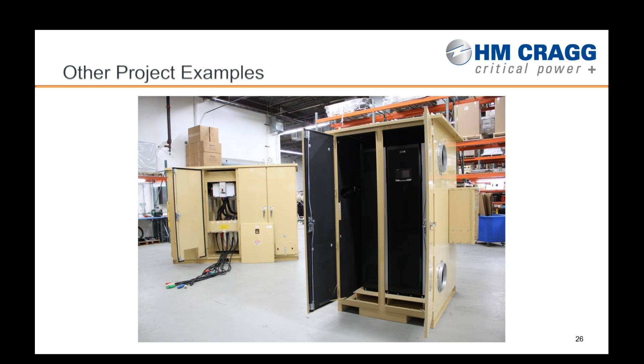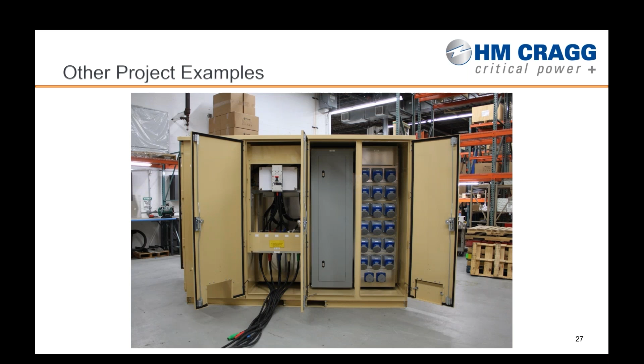This is my favorite part of the build, the switchgear and distribution cabinet. So we're taking those three sources. We have a manual transfer switch, an automatic transfer switch, and our UPS interconnection cabinet, which all these cam lock connectors are coming through. On the front side is a distribution panel with 20 protected load circuits with pin and sleeve connectors. And what we don't see on the back side is another panel, identical, with 20 unprotected load circuits, which they utilize to power their mobile HVAC units and things of that nature.